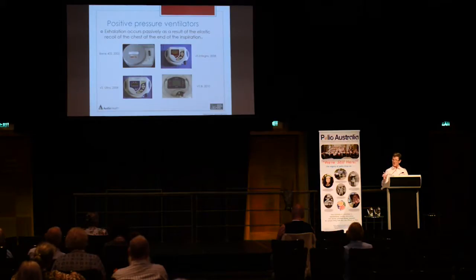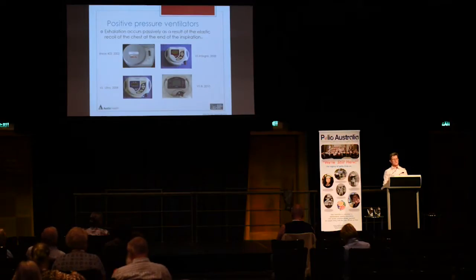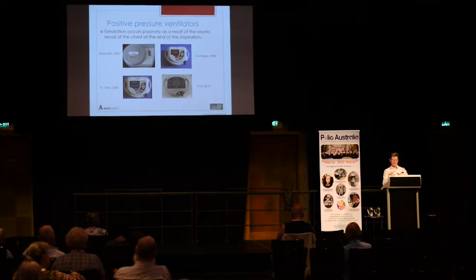The VS3 has multifunctions, so you can use it in bilevel mode or in volume mode, and you can have a number of different functions. So the ventilation has become more sophisticated over time. So the Breas 403 was a very straightforward machine. It pushed air in and then let you breathe out, but it didn't do anything else. The VS3 will give you a breath of a particular size for a particular duration with a particular flow pattern, and there's many more things that you can adjust to customise the ventilation to the individual's needs rather than just having a machine that just blows air for a set time.